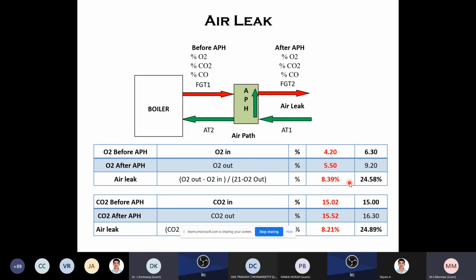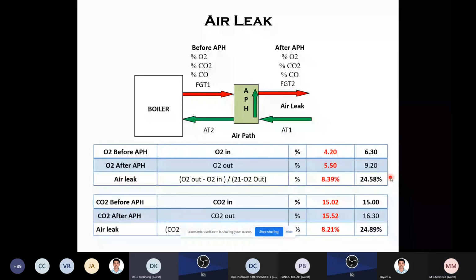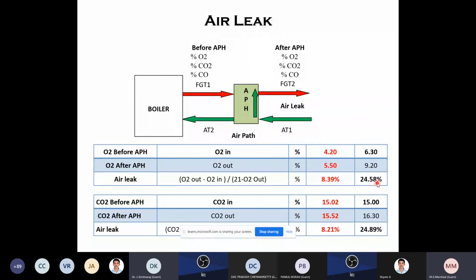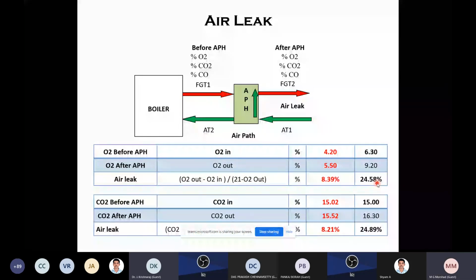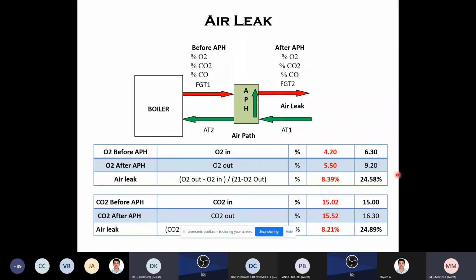So when you measure all these things, the energy audit team can recommend replacement of the baskets or replacement of the air preheater system itself, either basket or the seals for the leak. They can consider it. If the leak is more than 10%, they can very easily recommend arresting the air leak by changing the sealing. Changing is not a very big matter, it can be done. So in this way, we are able to understand.